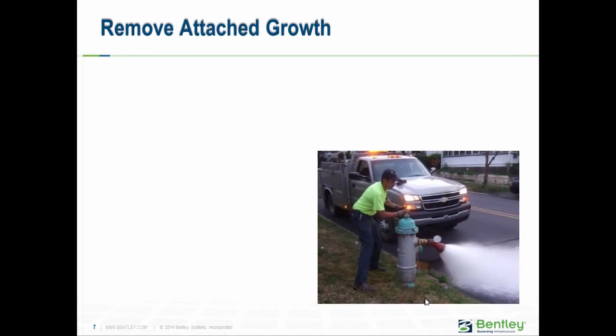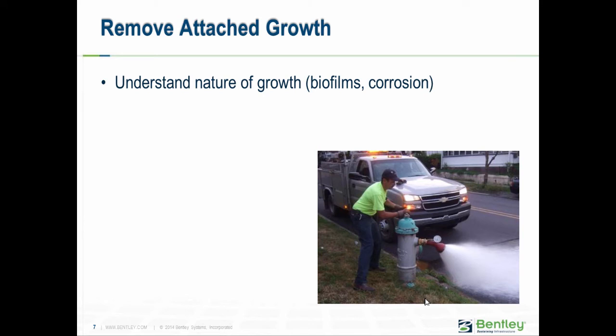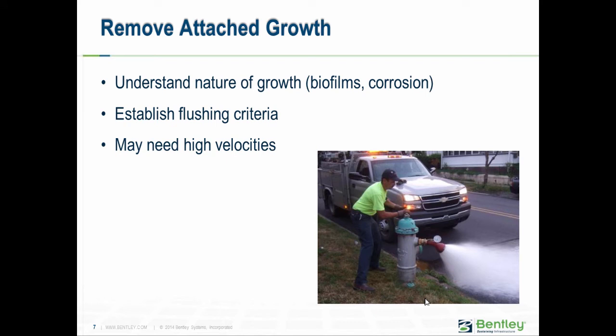When it comes to removing attached growth, you need to understand the nature of what you're trying to remove. Do some pilot areas using different velocities to see whether changing velocity changes the biofilm in the pipe. Some suggest you can remove tuberculation or corrosion products with flushing, but usually you can't get a high enough velocity. You may be able to remove some loose scale, but for most attached growths the velocities and shear stresses required are too great — you need something like pigging or scraping. First, establish flushing criteria: what distinguishes successful flushes from unsuccessful ones?